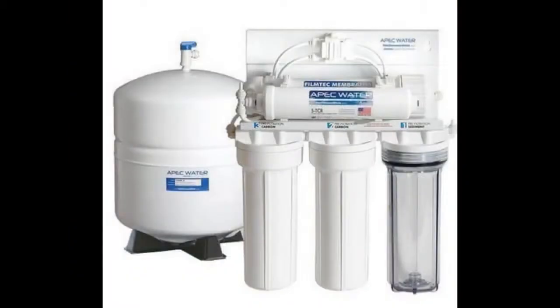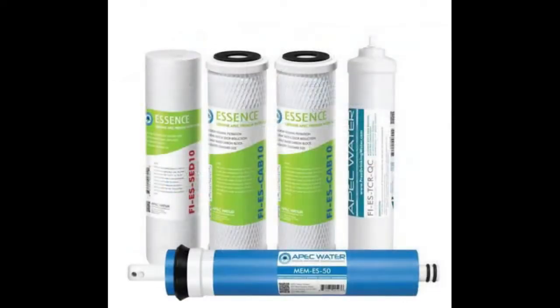The next issue we will discuss will be either low water or slow water supply. This is indicated by when your system runs for 10 to 15 seconds and then shuts off, even though the controller is calling for humidity, and then will run after a short period of time for the 10 to 15 seconds again. The low water and slow water issues can typically be fixed by replacing your filters in your reverse osmosis system to allow for a better flow of water.